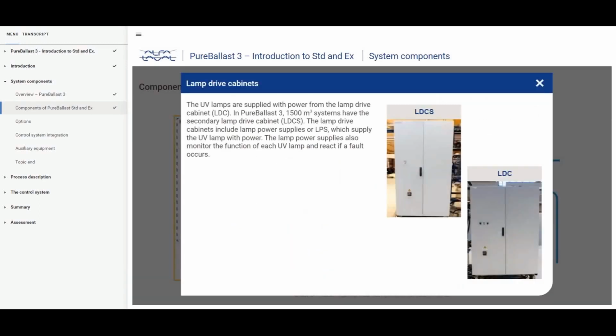The UV lamps are supplied with power from the lamp drive cabinet. In Pure Ballast 3, 1500 cubic meter systems will have a secondary lamp drive cabinet. The lamp drive cabinet includes lamp power supplies, or LPS, which supply the UV lamp with power. The lamp power supplies also monitor the function of each UV lamp and react if a fault occurs.